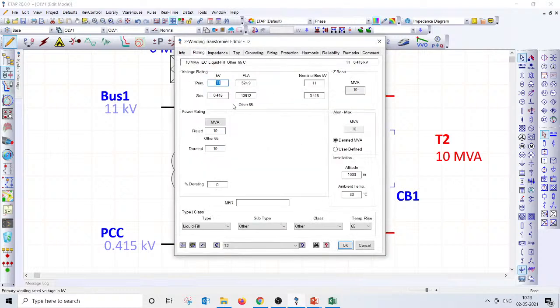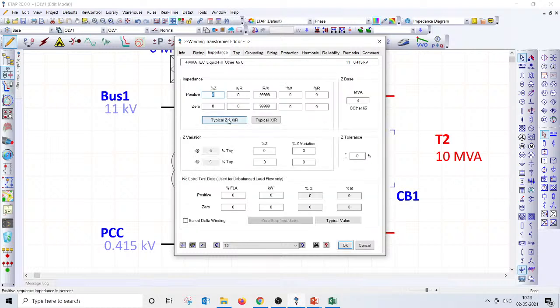So as we have seen, up to a maximum of 4 MVA we can go, and 4 MVA results in some current, and you can go with that kind of breaker. And if you are going with typical impedance, which I used to refer to always, you should not use typical impedance in IEC as per ETAP, because ETAP refers to the old IEC standard, and you need to take a new reference, or you have to take the value from the FAT report. How to identify the ideal impedance of the transformer: you need to perform load flow, short circuit and motor starting, and identify the optimal transformer impedance.